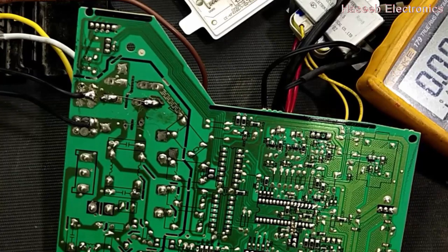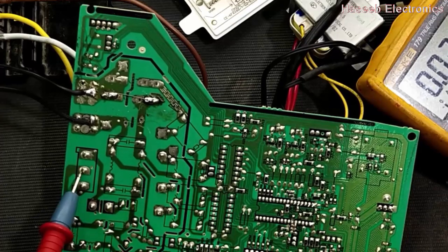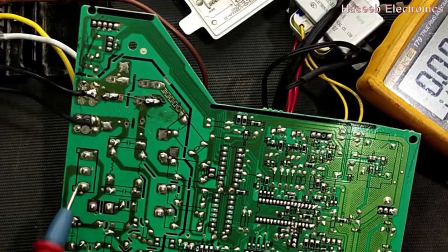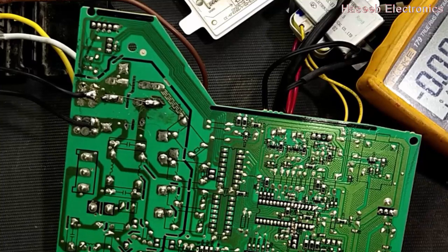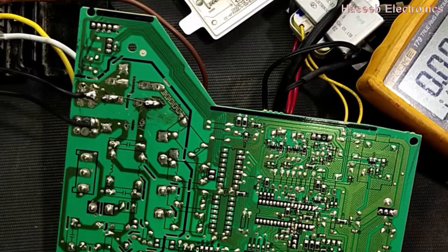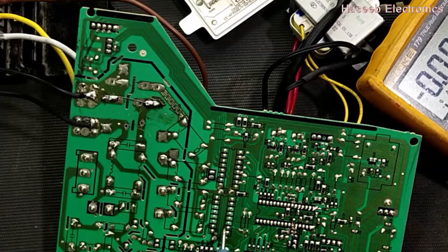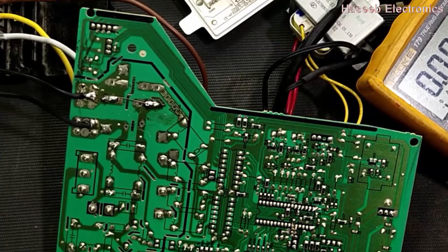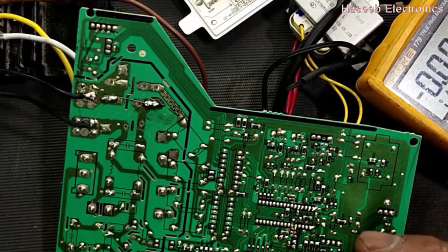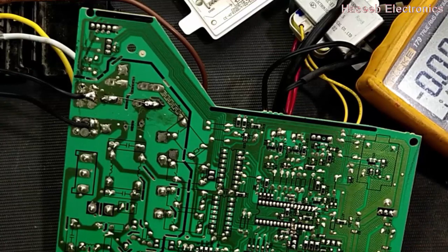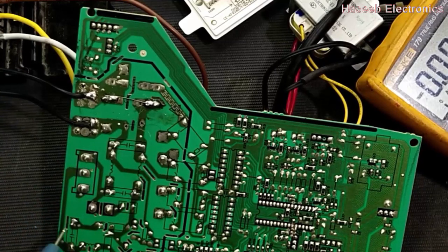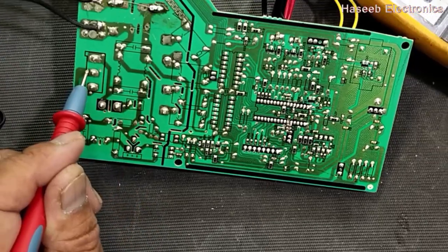Terminal 2 of the triac, through this choke, is connected to the center pin of this connector for the blower fan. When it receives a signal, an optocoupler signal, here we have this 6 pin optocoupler, it will drive the gate. So this ULN2003 will drive this optocoupler. The optocoupler will drive this triac, and it will switch the voltage, not rectify. It will make a controlled switching. Depending on how much pulse arrives at the gate, it will allow the voltage to pass to the blower fan, and the fan speed is controlled.